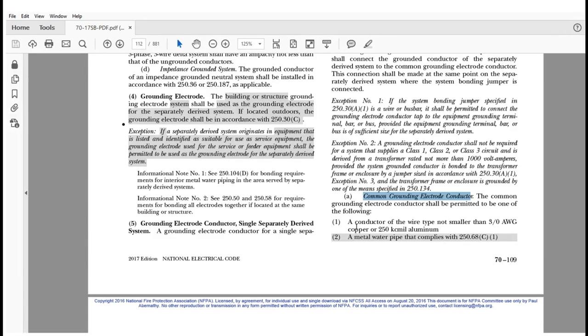Well, in the 2014 code, it stated that this common grounding electrode for multiple separately derived systems was permitted to be either the following. One, it could be the wire type, like we said, not smaller than 3/0 copper or 250 kcmil aluminum. That stayed. And it also said, or the metal frame of a building or structure that conforms to 250.52(A), which ironically is an electrode. And at this point, we've established that 250.68 is going to take care of that as far as extending the electrode now. So it really isn't an issue of the metal frame being the electrode anymore, it's that extension.